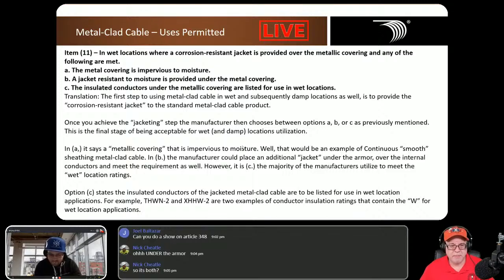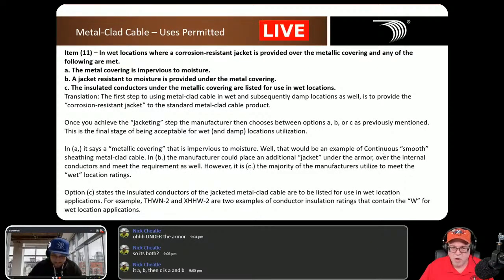The W is what creates the wet location rating. And you notice in A, it says metallic covering that is impervious to moisture. Well, that means examples of, again, continuous or smooth metal-clad cable. So that would be an example of that. In B, the manufacturer could place an additional jacket under the armor over the internal conductors and meet the requirement as well, like we just said.